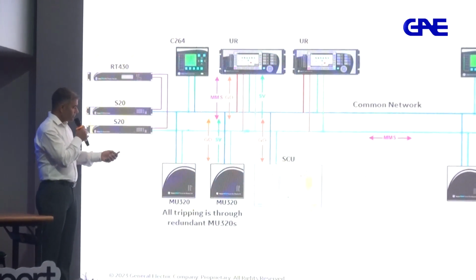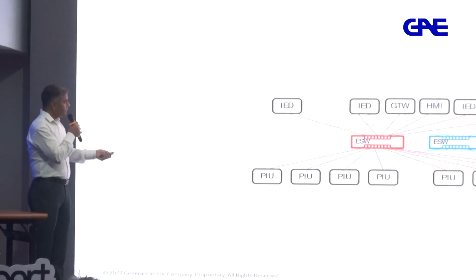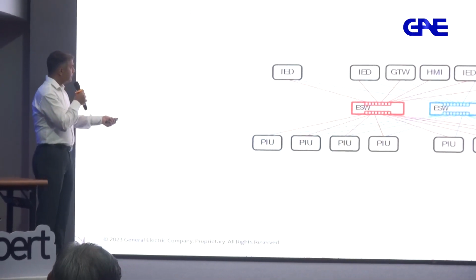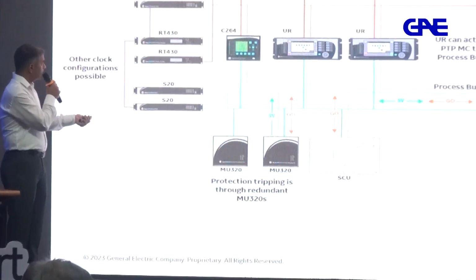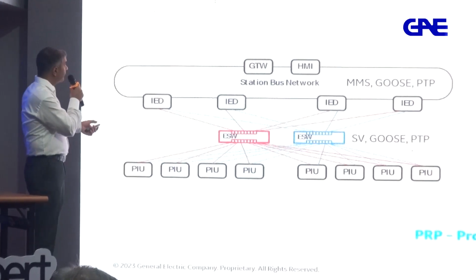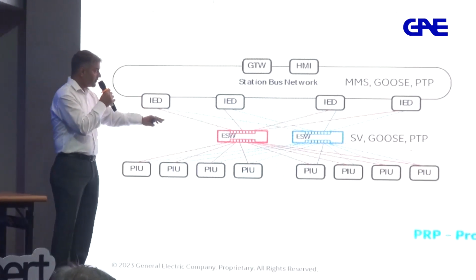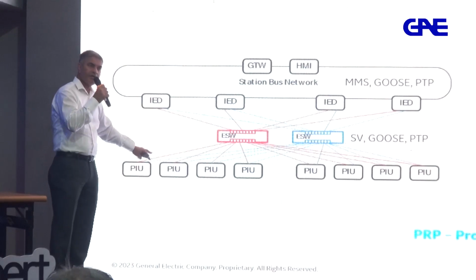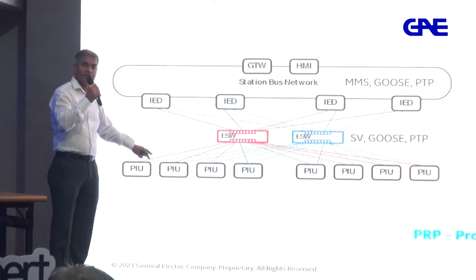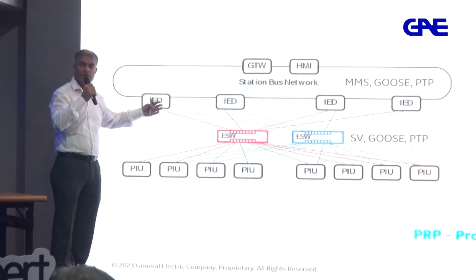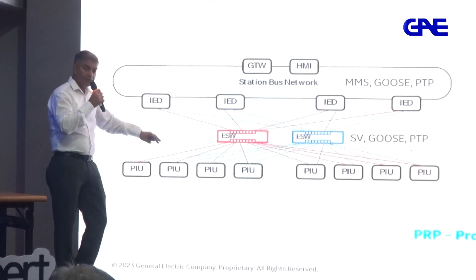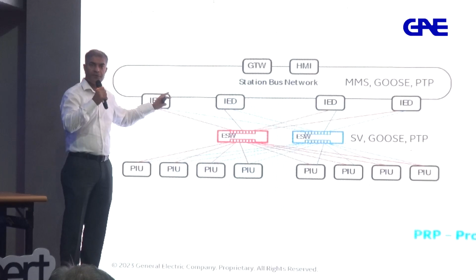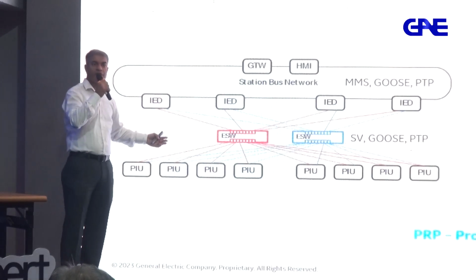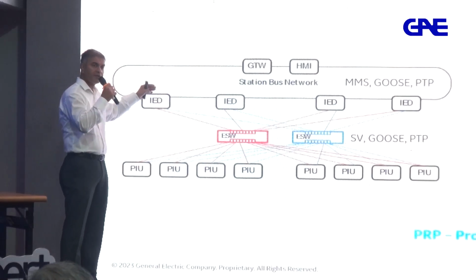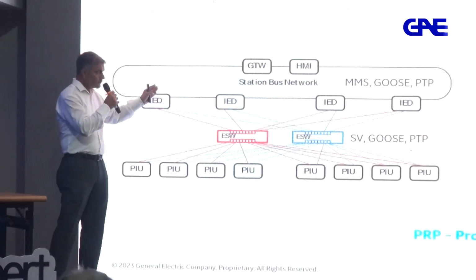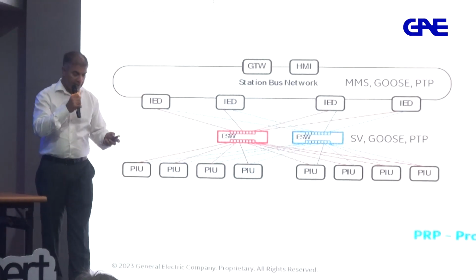Or you can possibly have a separation between station and process bus, but have one connection between station and process bus just for monitoring purposes, because you need to access your process devices through HMI. So you need to monitor their health, and pass some GOOSE messages from station to process. So you can also have one link between process and station bus.